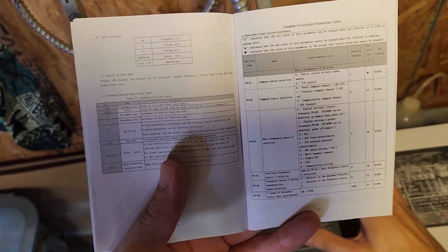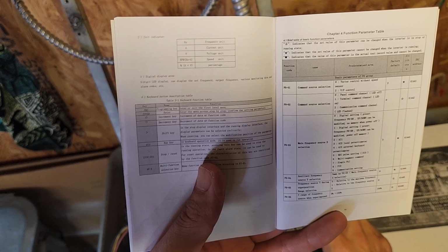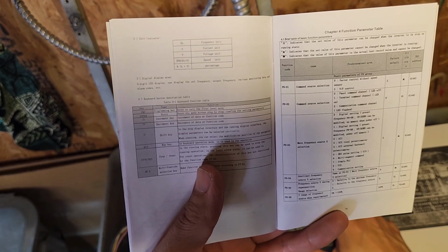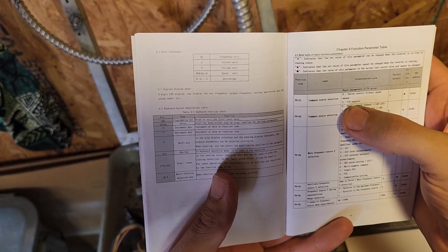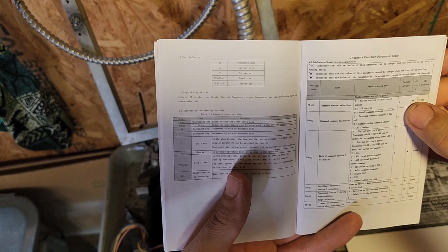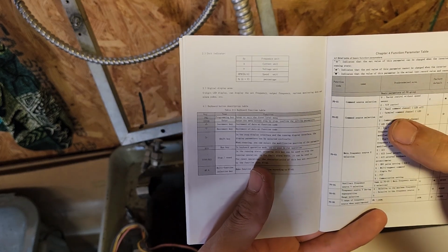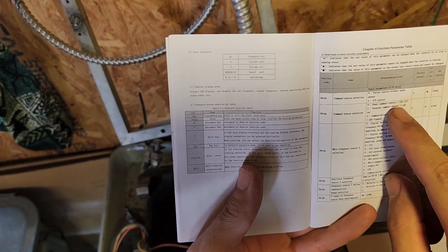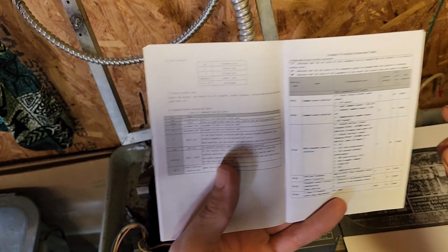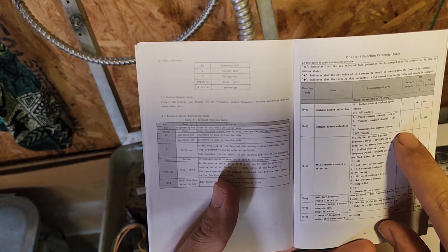So we gotta go here and then we want to go to P0, P01. It's set for 2. We're gonna leave it at 2. I looked through most of these and I think the defaults, except for one, are pretty good. Command channel, I think they're talking about how the VFD receives commands, so this panel here is what it's talking about in 0. So it's already set to 0. We're going to leave it there.